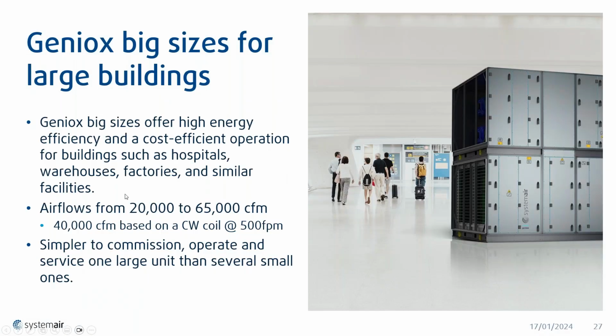There is one thing that I'd like to bring your attention to: as soon as we start getting to the bigger sizes of the unit, we do have our airflows from 20,000 CFM. These are our big double stacked units, which you see over there, which have the wheel or the recovery in there as well. However, if you do have a chilled water coil in there, normally when I'm designing the AHUs and specifying and working with them, I like to keep that down to 500 to 550 feet per minute. I don't like to go over that myself because you are going to get some carryover off the coil. You can obviously extend that from 550. We would normally recommend that you put in a droplet eliminator.